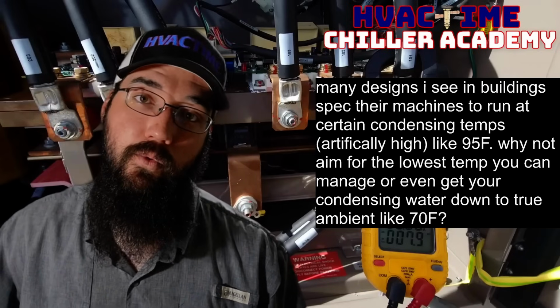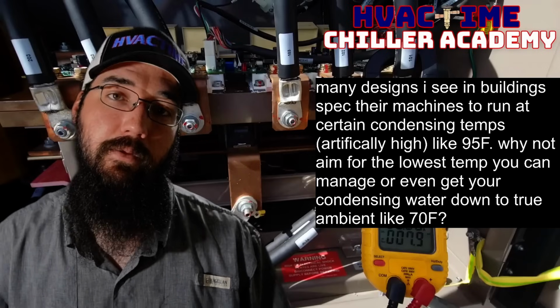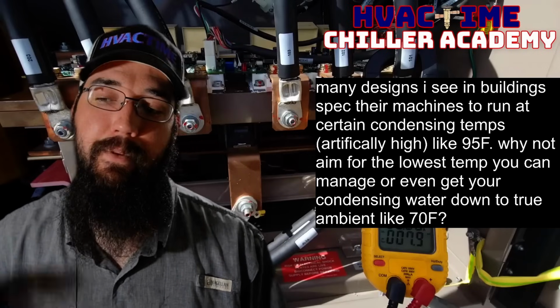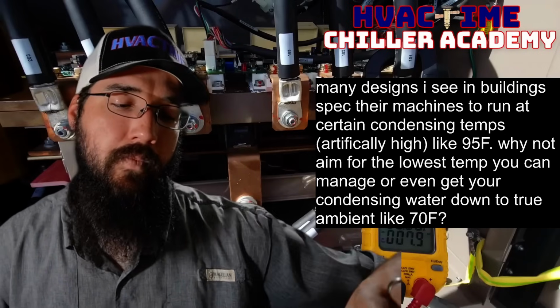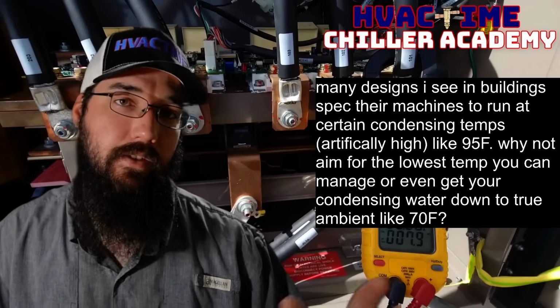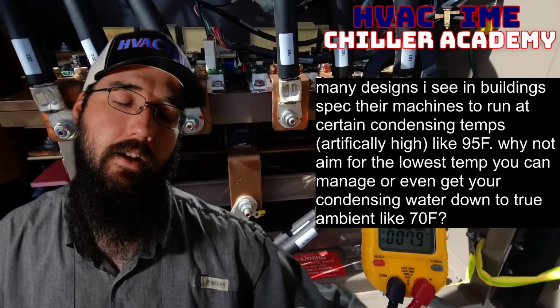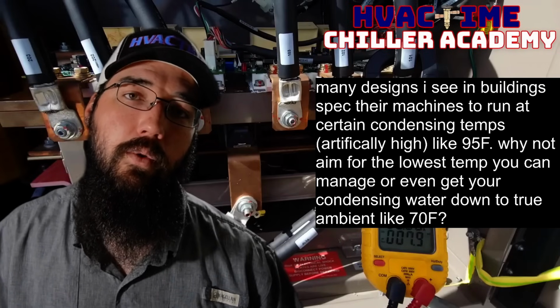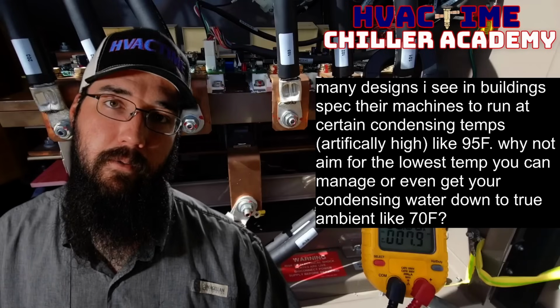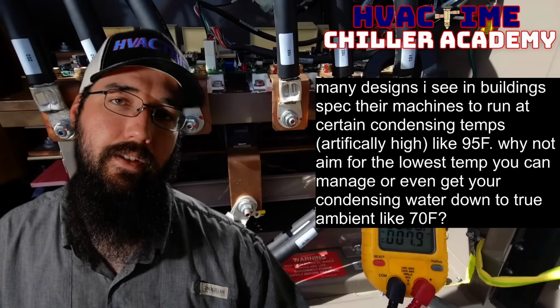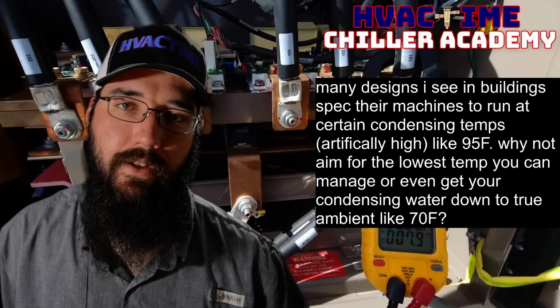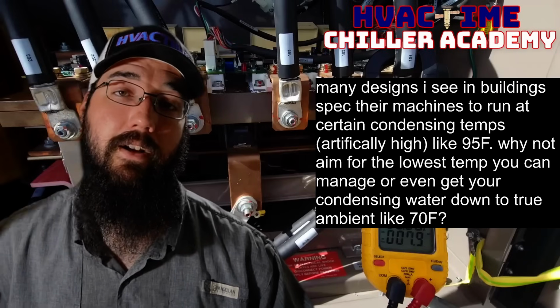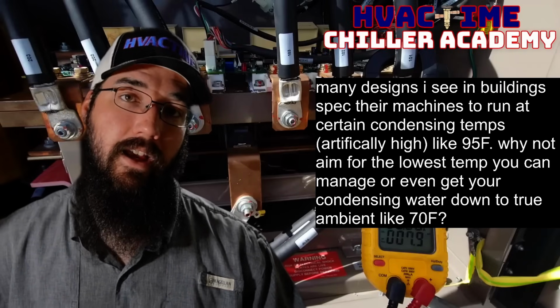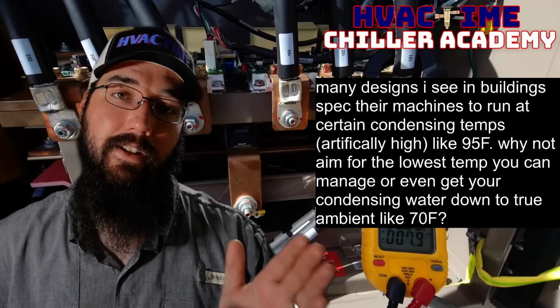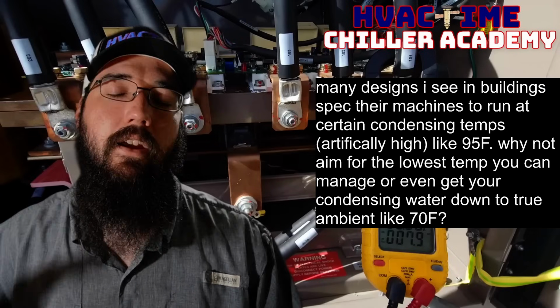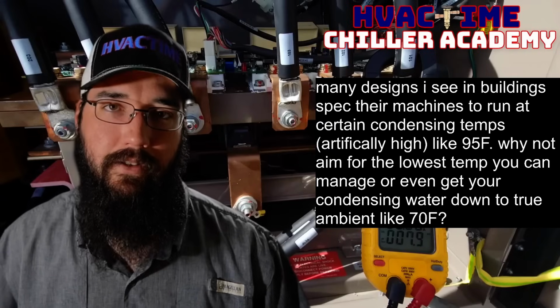temperature, but they don't do quite as well at the higher temperatures most of the time, especially if I've got a site that doesn't typically load that chiller up all the way. So with a YK, I would set the same formula as to how we're calculating it, but I would set that lowest set point minimum to about 65. Now, York says you can go as low as 60, but I prefer about 65, but I'll cap out at 80. So I'll let that one swing between 65 and 80 instead of the 75 and 85 to 90 with a Trane, as just two baseline examples here.